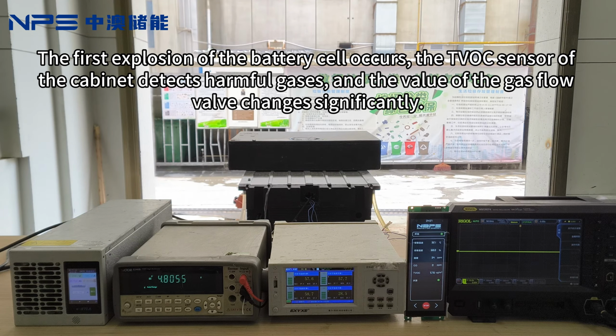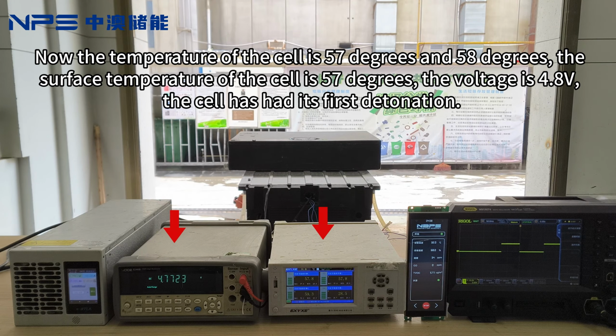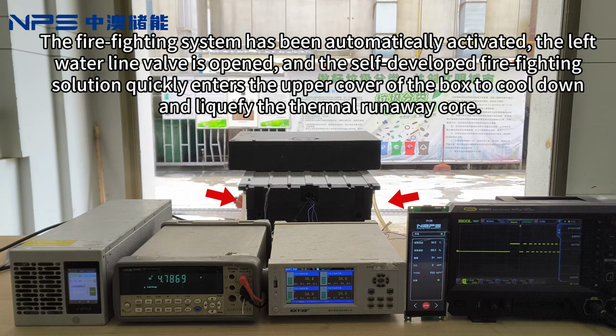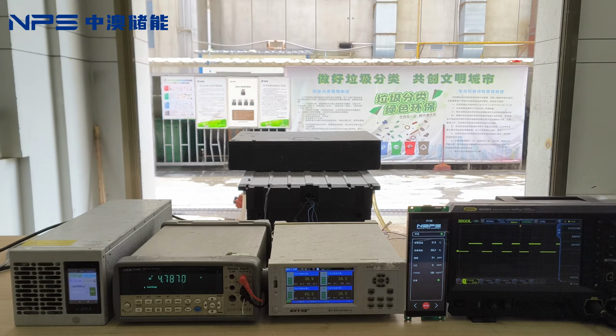When the first leakage of the cell has occurred, the TVOC sensor in the box has detected harmful gases, and the gas flow valve value has changed significantly. Currently, the temperatures of the pole columns of the cell are 57 and 58 degrees Celsius. The surface temperature of the cell is 57 degrees Celsius, and the voltage is 4.8 V. Since the cell has had the first deflagration, the firefighting system is automatically activated, and the water valve on the left side is opened, and the self-developed firefighting solution rapidly enters the upper cover of the box to cool down and liquefy the thermal runaway cell.